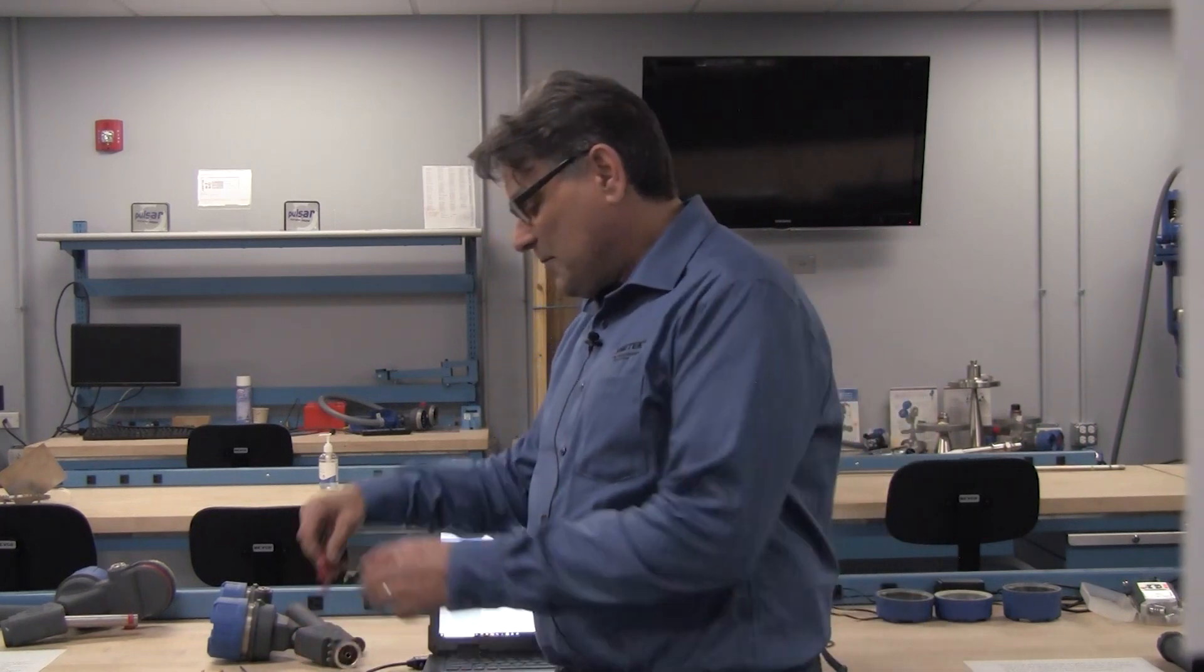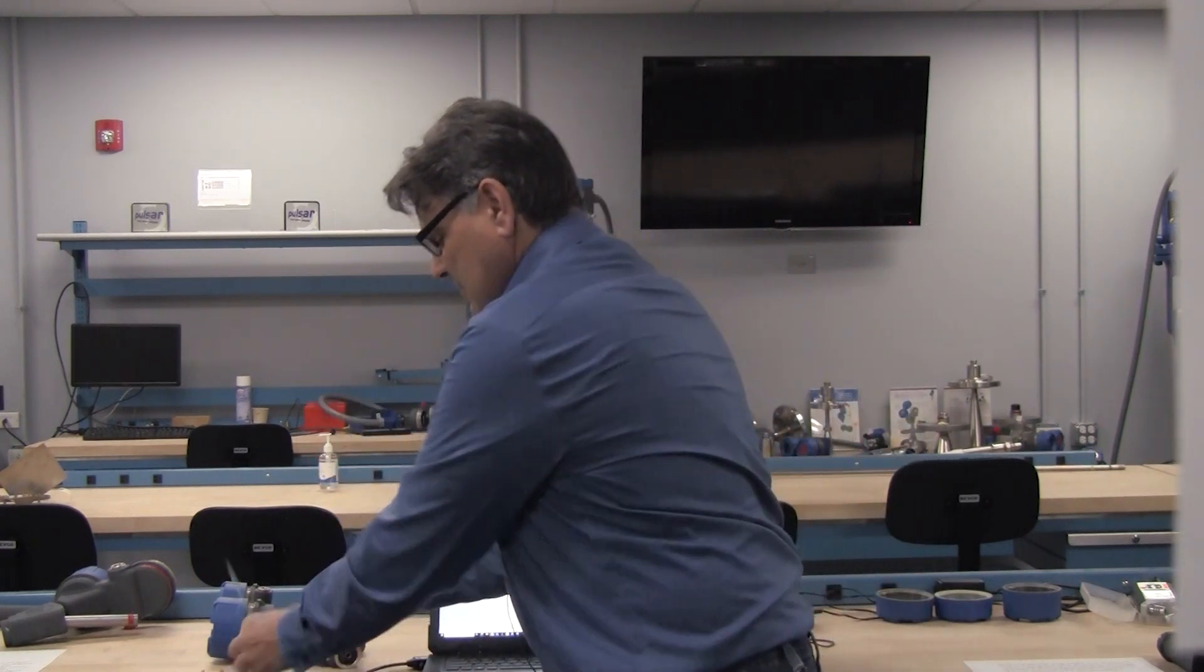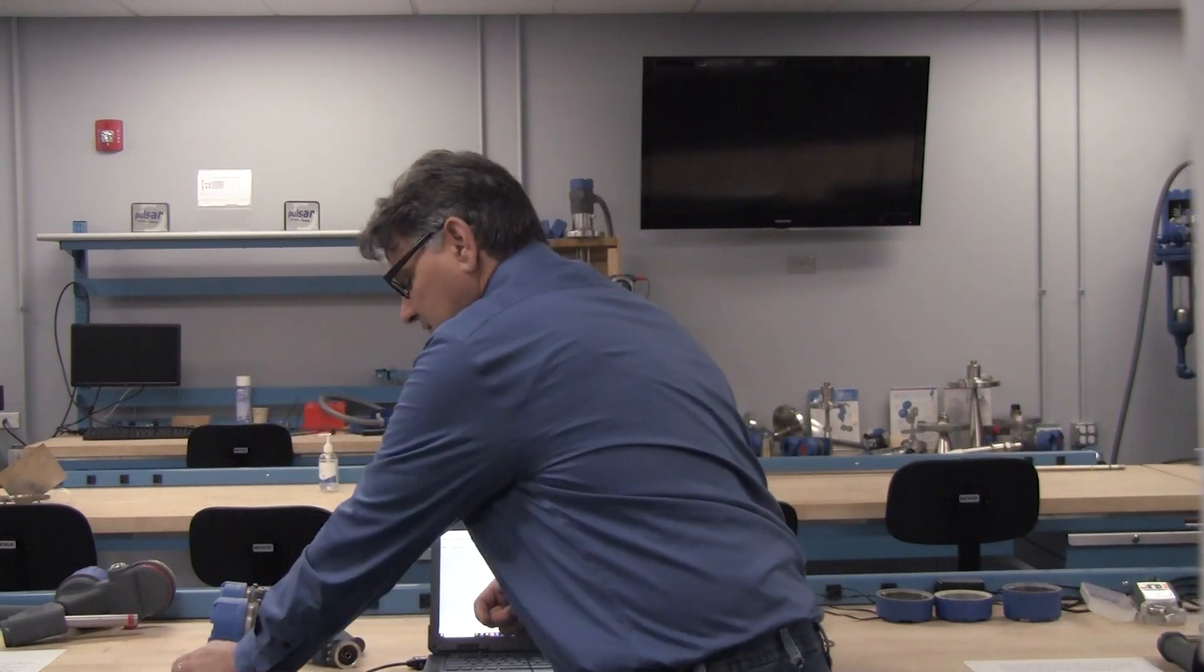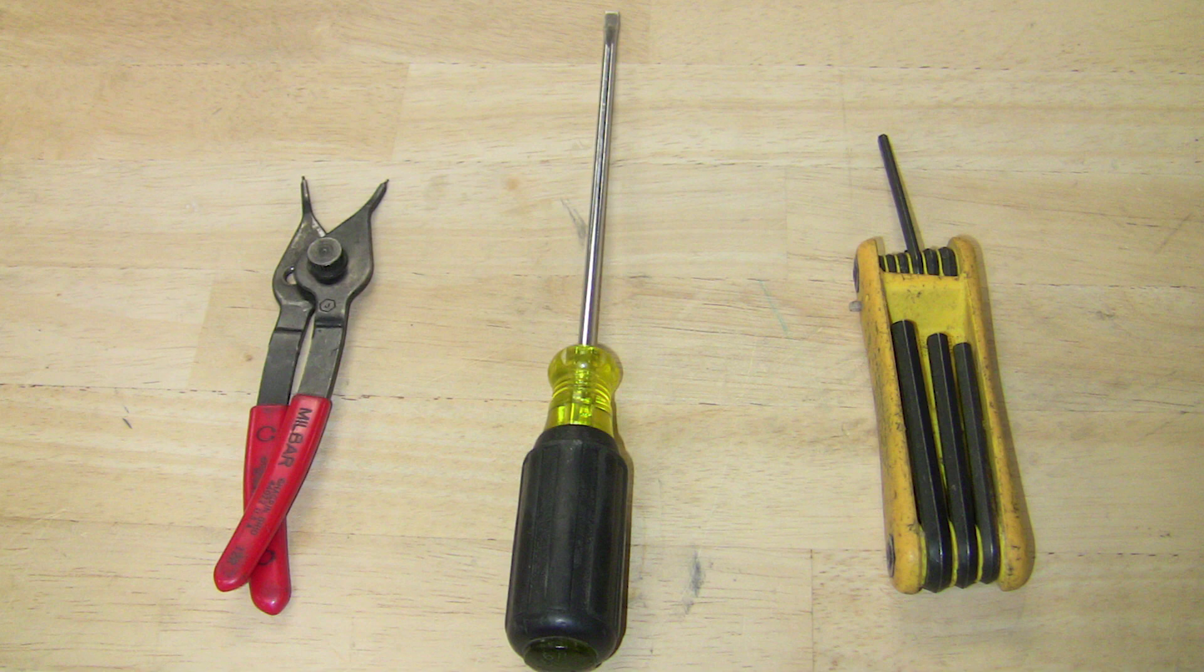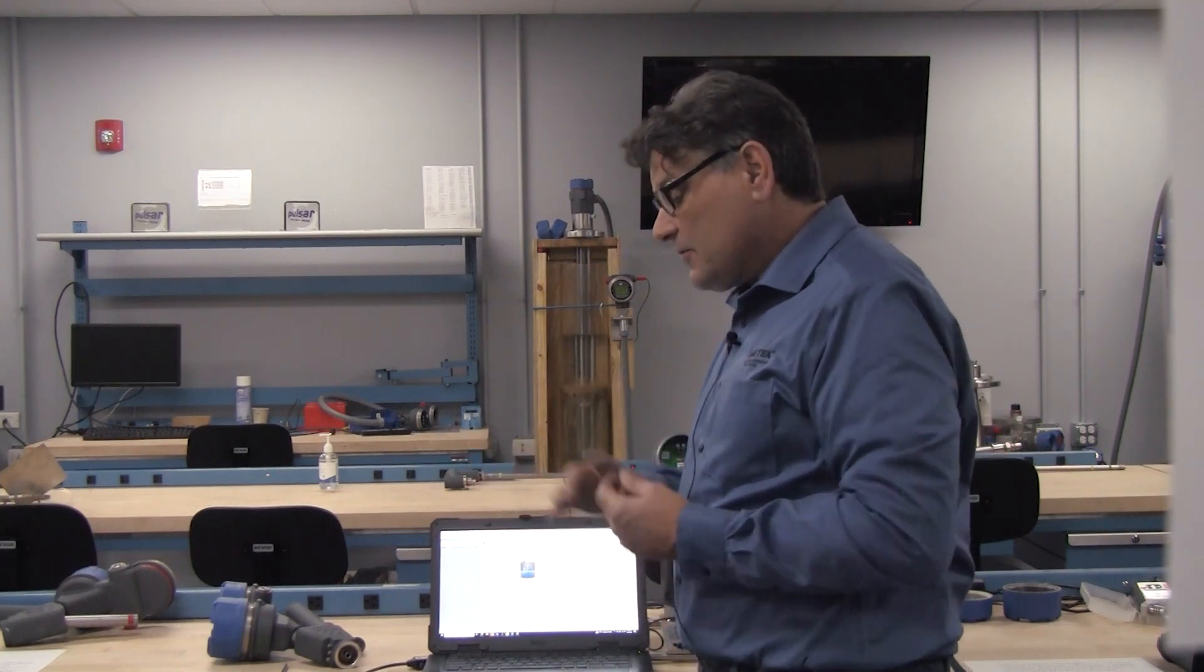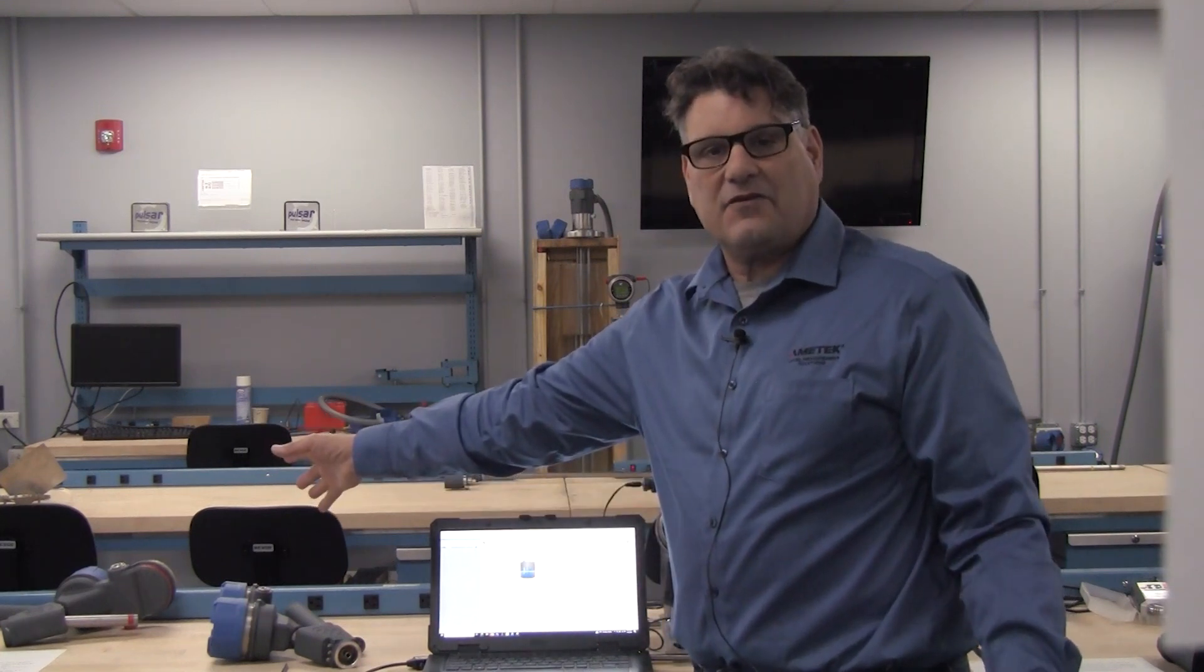The tools you'll need for the installation are snap ring pliers, a flat blade screwdriver, an eighth inch Allen wrench, and a laptop loaded with PACTware, a 250 ohm resistor, and a HART modem. Those are optional if you wish to use the laptop to set it up. You can also do the setup from the display of the transmitter.